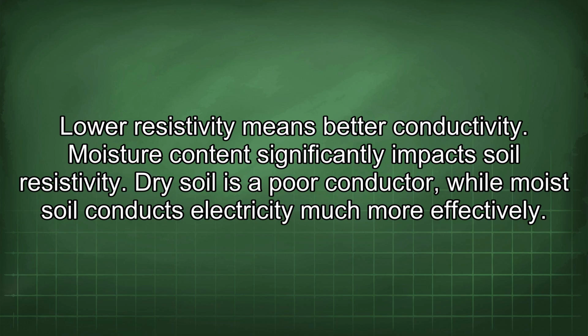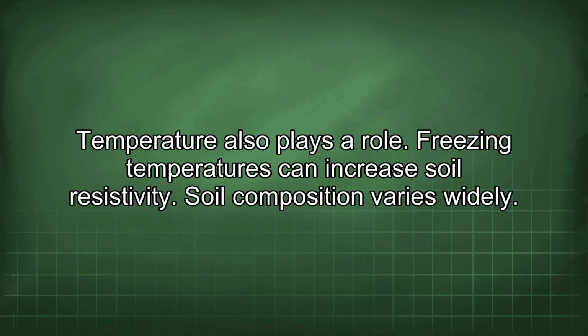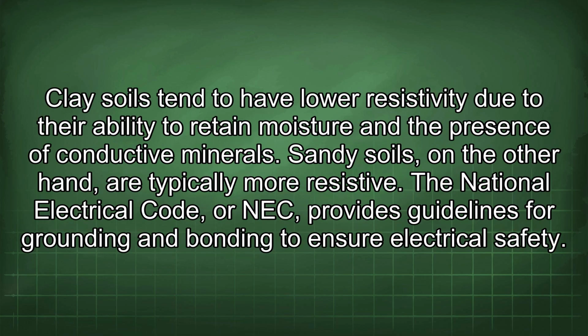Moisture content significantly impacts soil resistivity. Dry soil is a poor conductor, while moist soil conducts electricity much more effectively. Temperature also plays a role. Freezing temperatures can increase soil resistivity. Soil composition varies widely. Clay soils tend to have lower resistivity due to their ability to retain moisture and the presence of conductive minerals. Sandy soils, on the other hand, are typically more resistive.